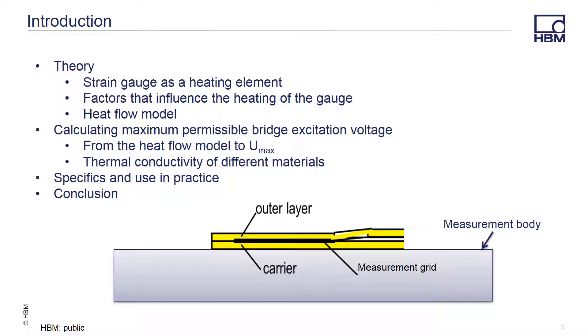Calculating the maximum permissible excitation voltage for a strain gauge is sometimes required. The data sheet included with a strain gauge will often include a suggested excitation voltage, but this value is based on a typical material and that may not match up with the material you are using. A strain gauge is basically a little heater — there is current flowing through a resistor. We will discuss the factors that determine the amount of heat generated, then go through the math to determine the excitation voltage based on the size of the gauge, its resistance, and the thermal conductivity of the material the gauge is attached to. Finally, we will go through a couple of examples and conclude.